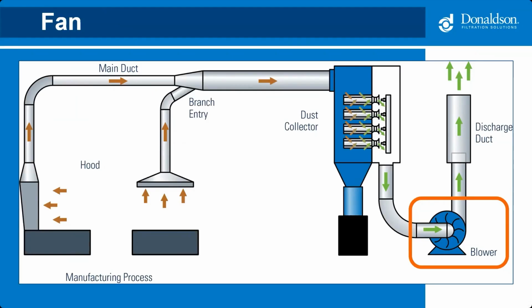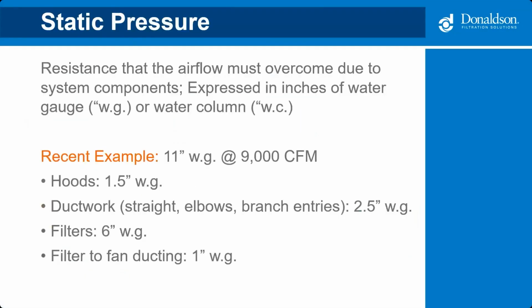When designing a system, the very last thing we do after completing all the airflow calculations is select and size a fan. A critical component of fan design is static pressure. It's basically the resistance that the airflow must overcome due to the system components. It's expressed in inches of water gauge or water column. And when we design a system, we calculate the total system static pressure so we can size the fan properly.